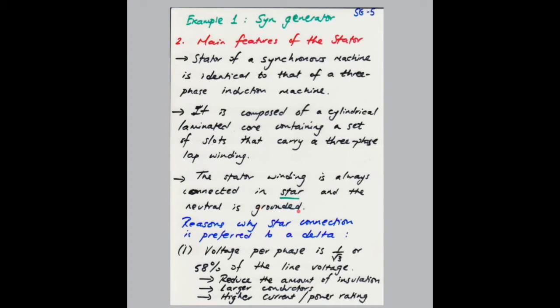So there are a couple of reasons why we connect it in star. The first one is, obviously, when you connect the machine in star, the voltage per phase is 1 over √3 times the line voltage. So that's 58% of your line voltage. Because the per phase voltage is lower than the line voltage, that allows for, firstly, a reduced amount of insulation. So the size of the insulation is reduced, right? And it allows for larger conductors because now you have more space. And if you have larger conductors, that translates to higher power rating or higher current, right?